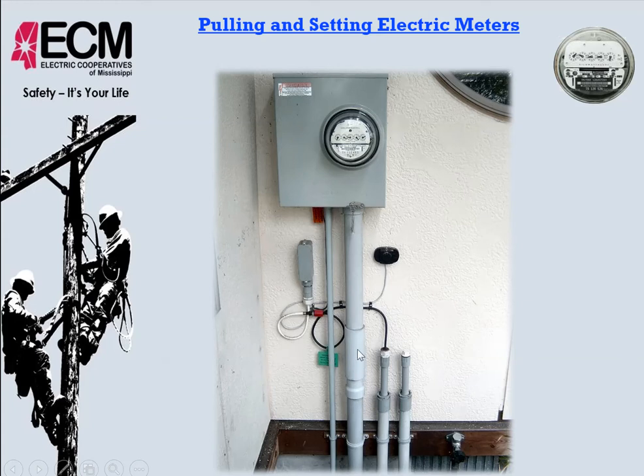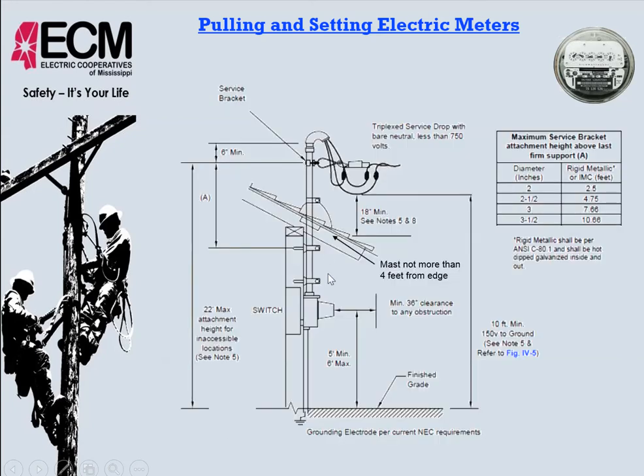Also, this is an expansion sleeve. The one that I showed you before, where the pipe had pulled through the knockout because of the settling of the ground, this is a sleeve right here that would help prevent that from happening. It's an expansion sleeve. It will slide a certain amount of distance to compensate for that settling of the dirt. But also, that's one of the reasons that you want to loop your wire up high in the meter base and come over the top, so as this settles down, we have some slack here. Okay? All right. So let's look at some clearances on a meter base, some things that we need to look out for.